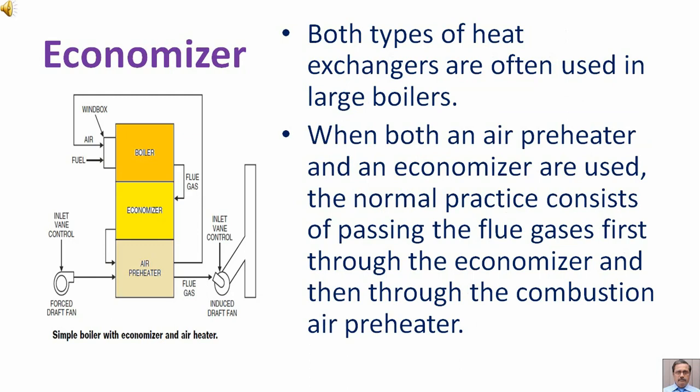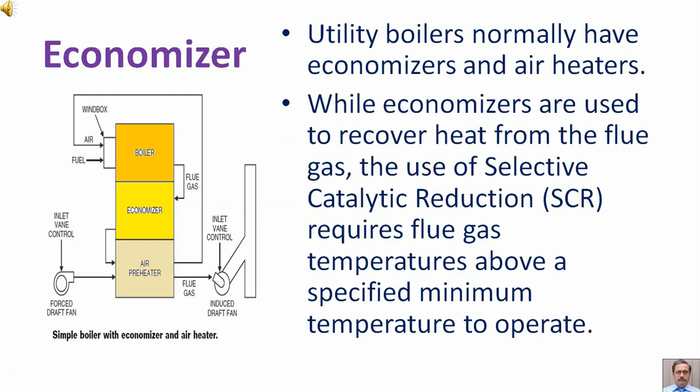Both types of heat exchangers are often used in large boilers. When both an air preheater and an economizer are used, the normal practice is to pass the flue gases first through the economizer and then through the combustion air preheater. Utility boilers normally have economizers and air heaters.